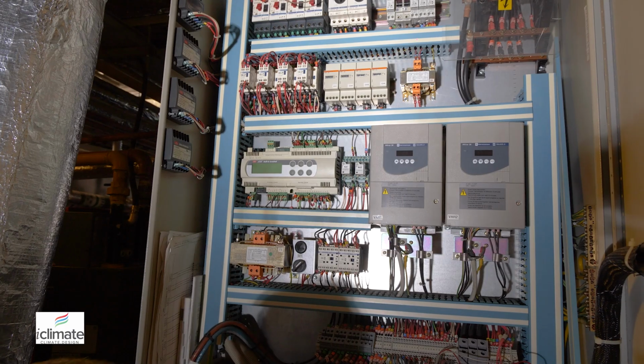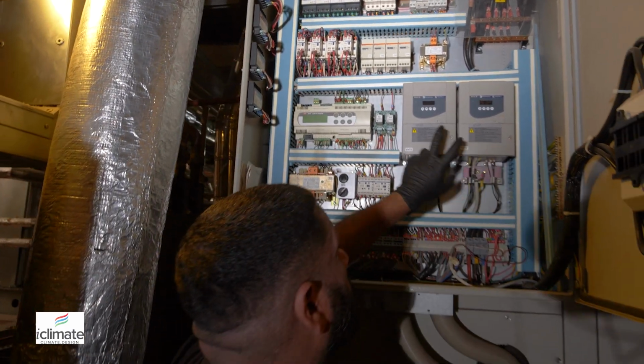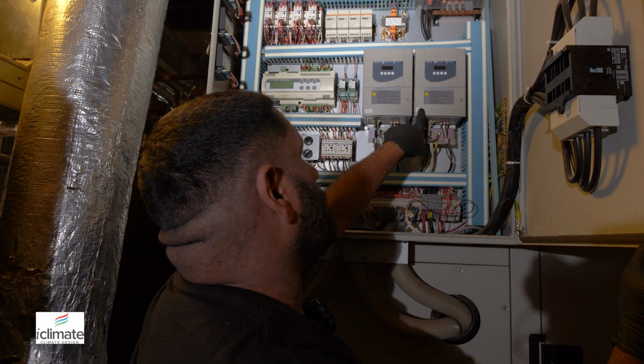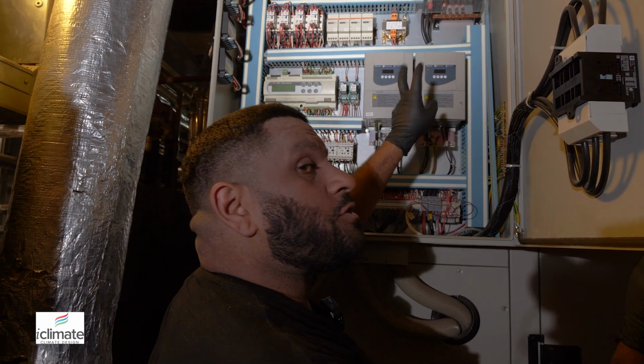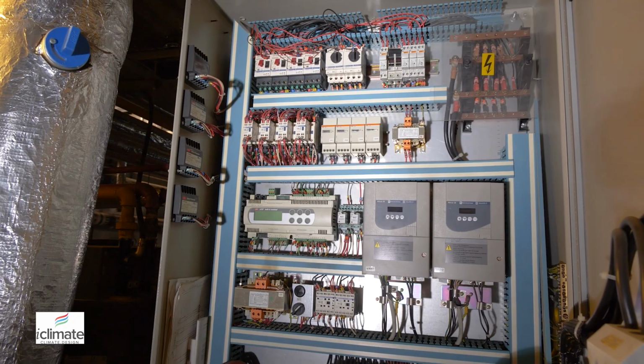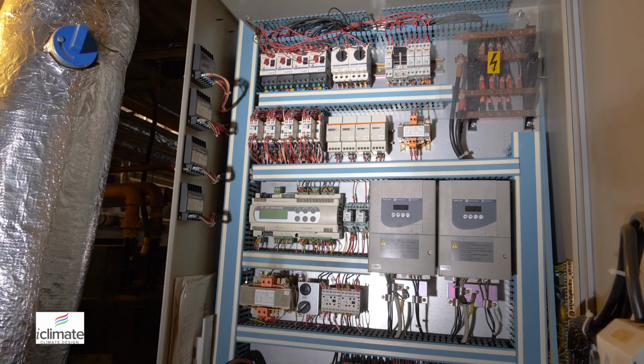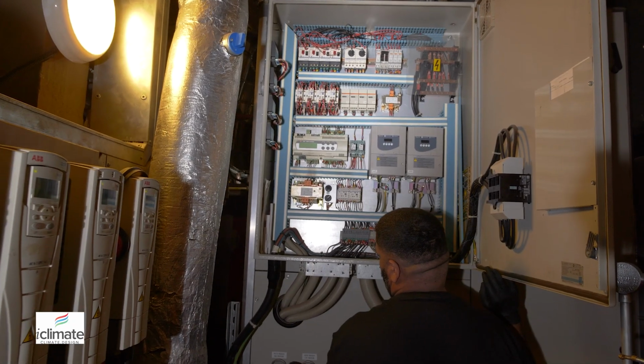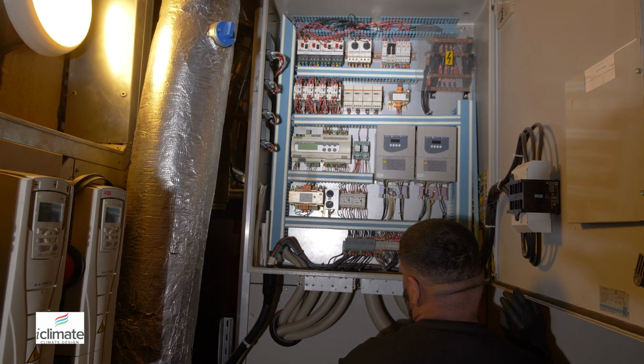So we've seen inverters that relate to air handling motors, and we've got inverters here, VAR1 and VAR2, which relate to the two compressors and the two circuits that are in this chiller. This chiller is really old. We've come to site and we found that the liquid filled gauges, some of them are reading low pressure, near zero on two circuits.